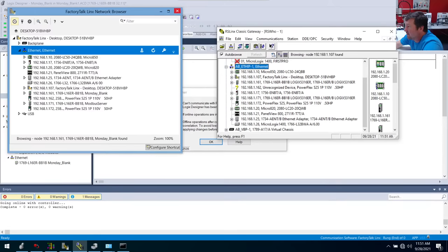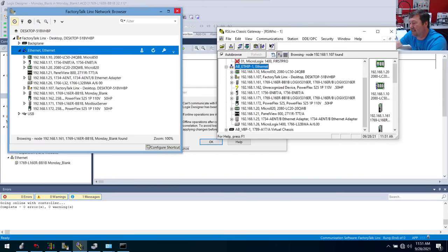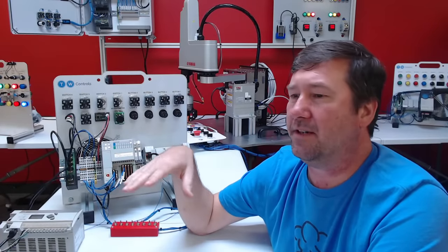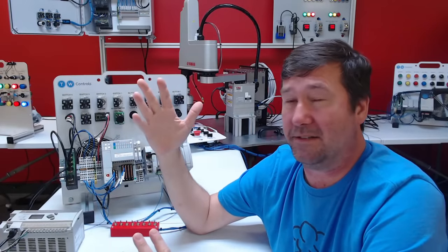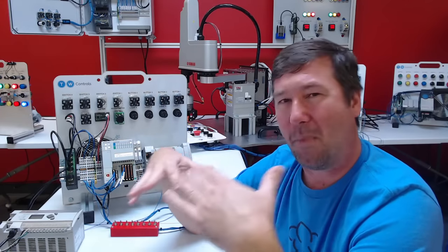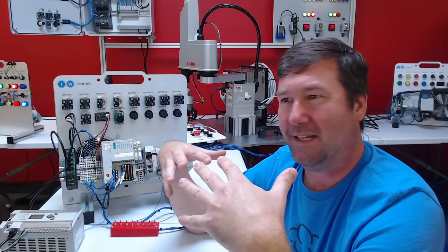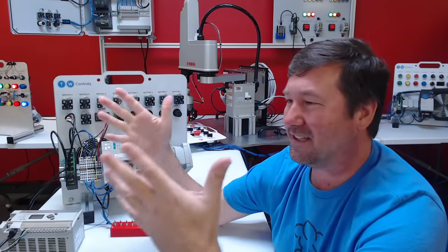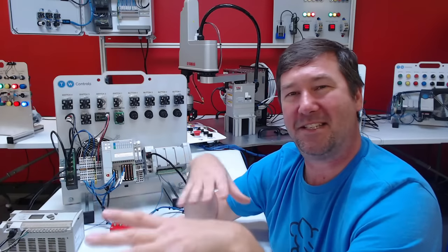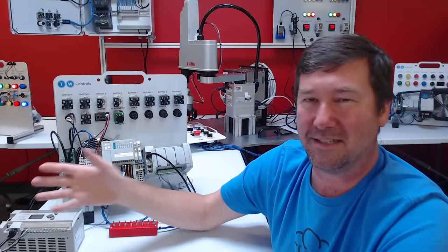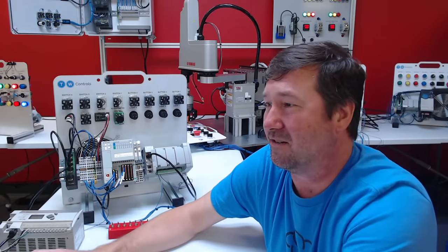We switched from RSLinx to FactoryTalk Linx because it works better, and it does — it does seem to be a little bit better at communicating. We started having some issues here at the PLC lab where we would get to almost just a marginal point, and if we added one more PLC to our network, it was like the Achilles heel. All of a sudden everybody started having Studio 5000 operating real slow, PLCs disappearing and reappearing. And we switched to FactoryTalk Linx, and yeah, that made it much better.